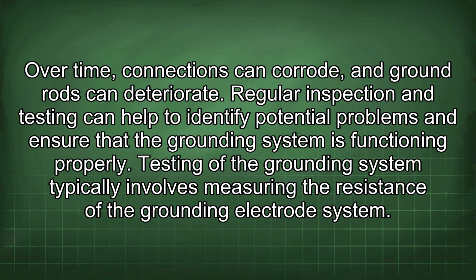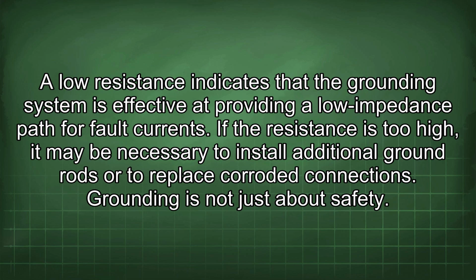Testing of the grounding system typically involves measuring the resistance of the grounding electrode system. A low resistance indicates that the grounding system is effective at providing a low impedance path for fault currents. If the resistance is too high, it may be necessary to install additional ground rods or to replace corroded connections.